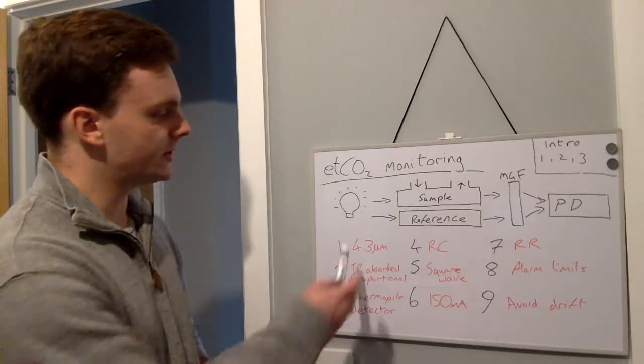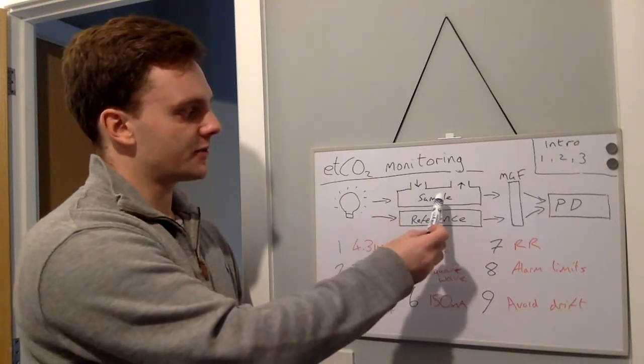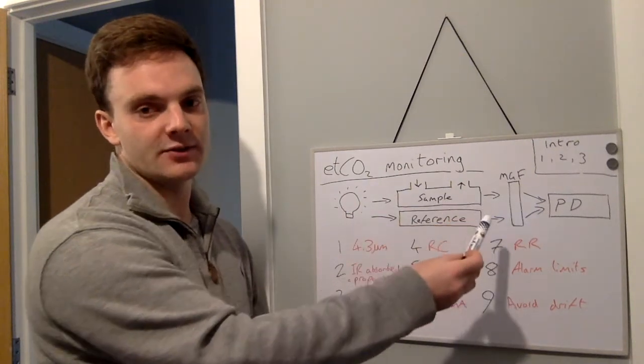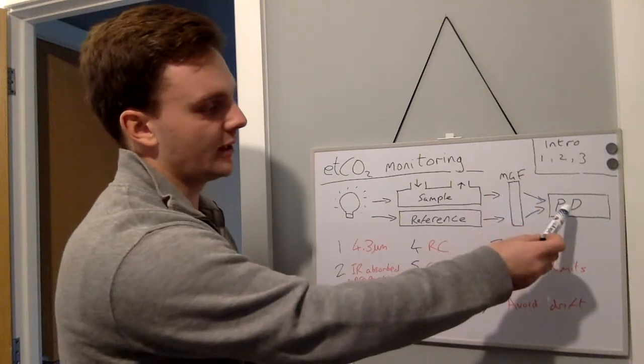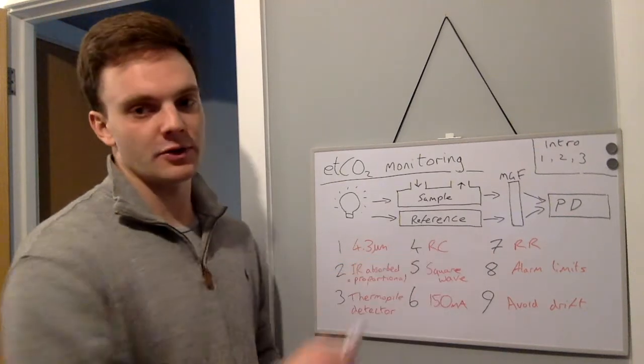So we look at this diagram here. We have a light source. The light source then passes through a sample chamber, a multi gas filter, and then will hit a photo detector. We have the same thing that happens through a reference chamber.